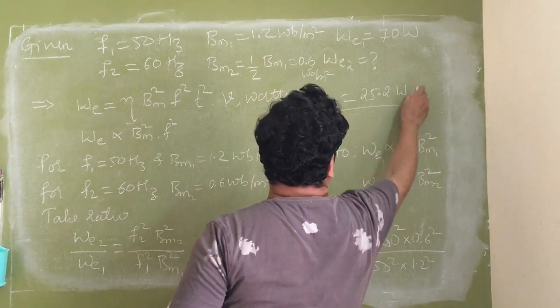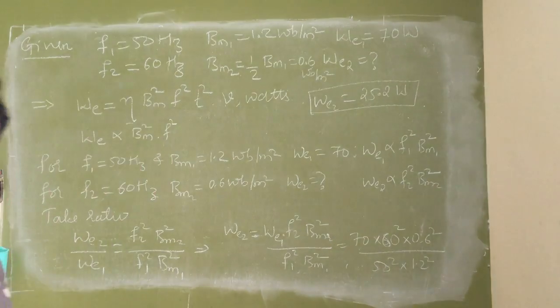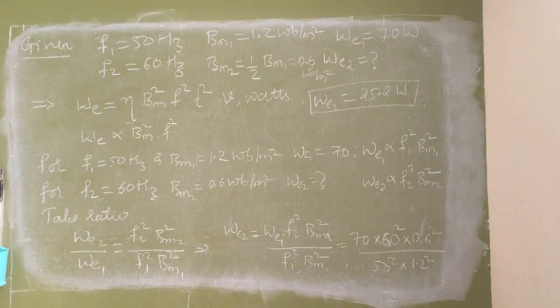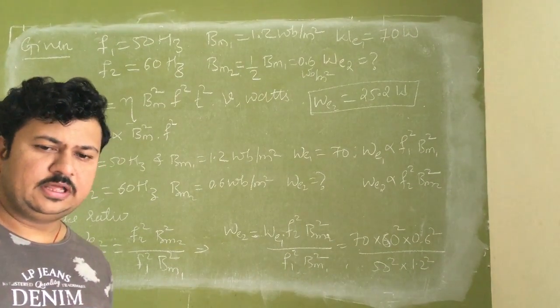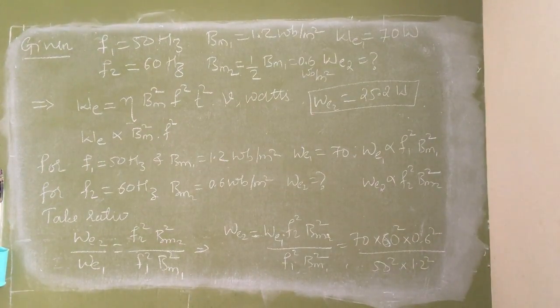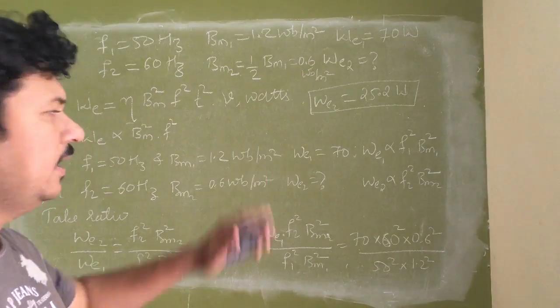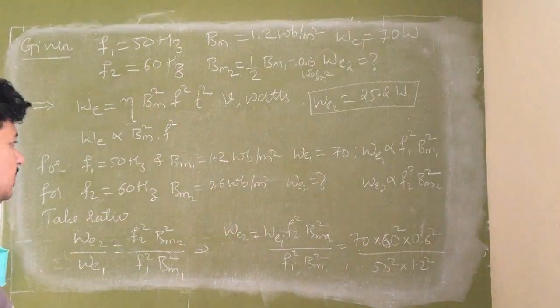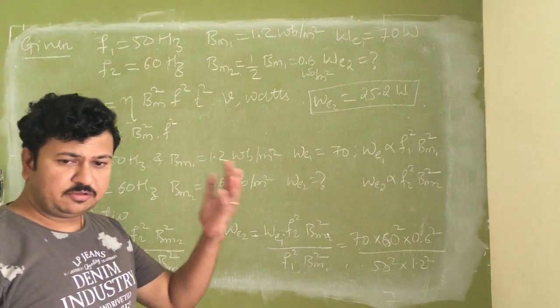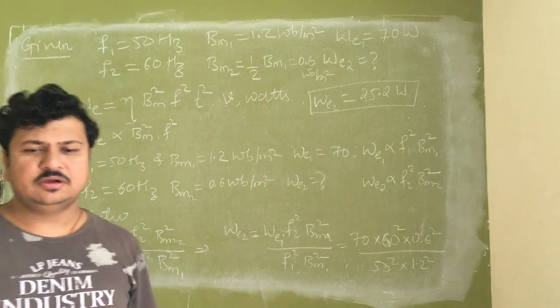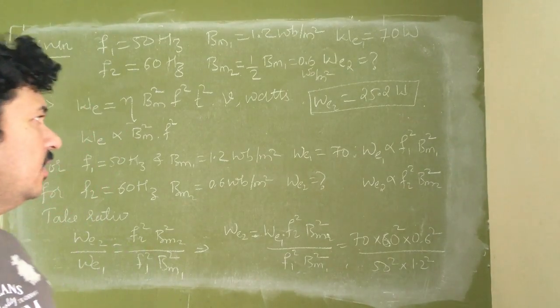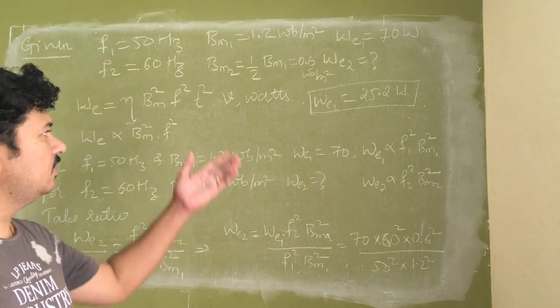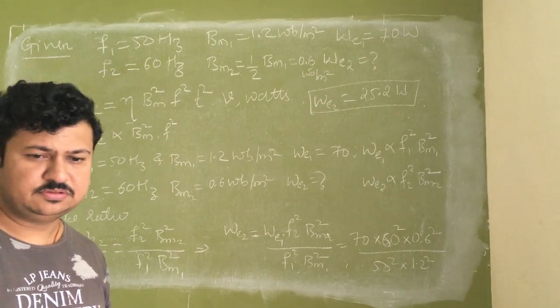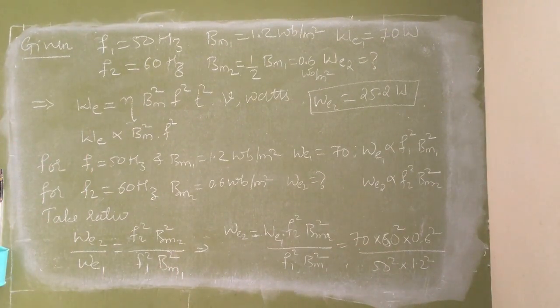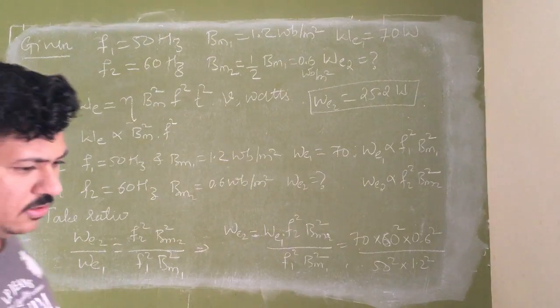Okay, 25.2 watts. So I am increasing the frequency but decreasing the flux density. Therefore, the effect is decreasing eddy current loss. There is no compulsion that when I increase frequency and decrease flux density, eddy current loss should decrease. It depends on by how much I am increasing the frequency and by how much I am decreasing the flux density. If the increase in frequency is double, then the eddy current loss may increase. Okay, so this is how the eddy current losses vary.